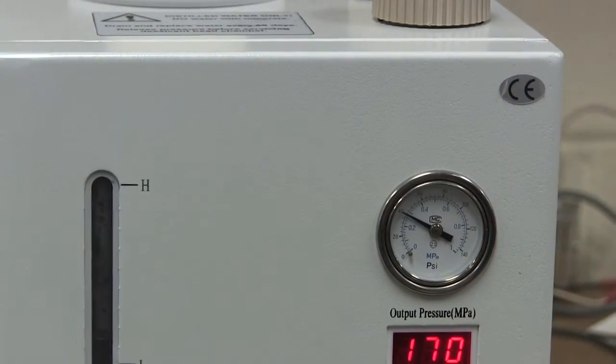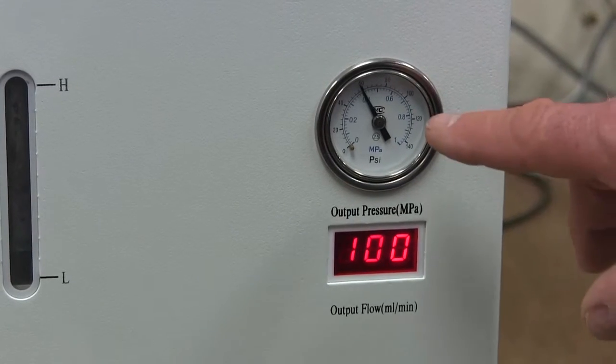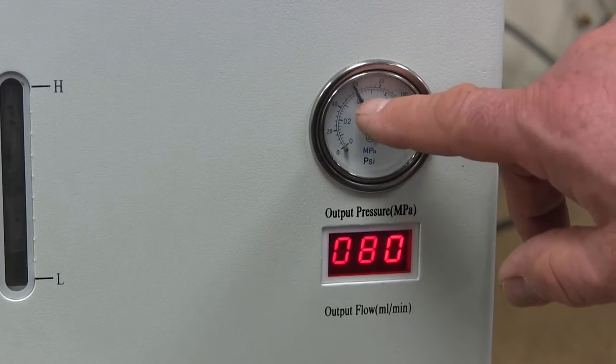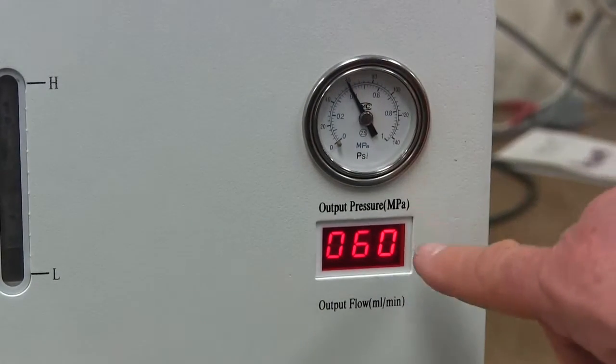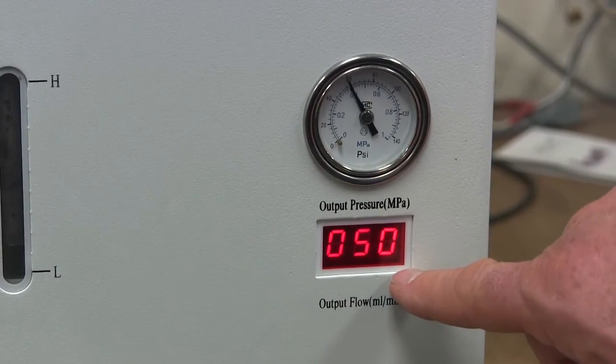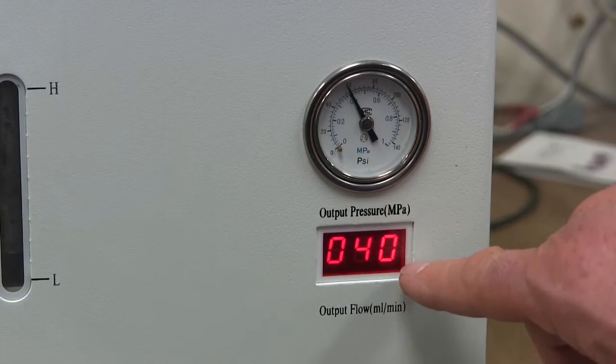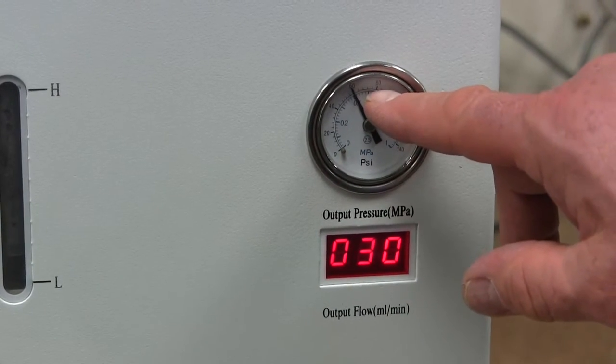Okay, so you see how as the pressure is getting close to 60 psi, how the flow is dropping. So it'll drop right to zero as it pressurizes up to the set point.